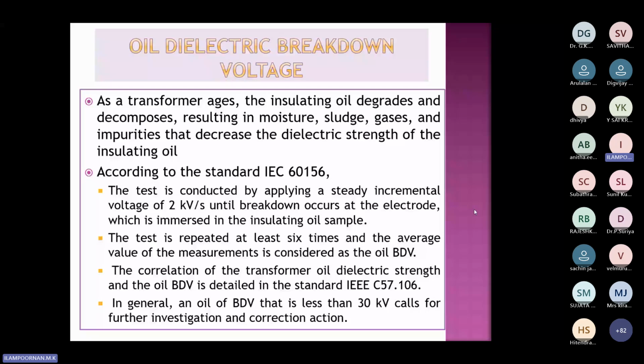You take the electrode mentioned in almost all the standards. There are specifications for the size of the electrode and the distance between electrodes. You apply voltage and see what the breakdown voltage of the oil is, as it has to break down between the electrodes.